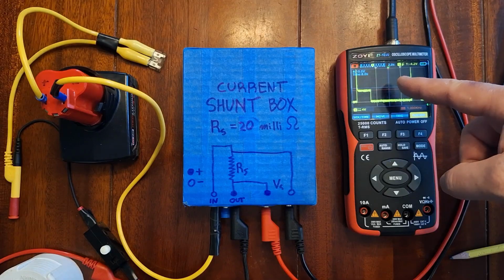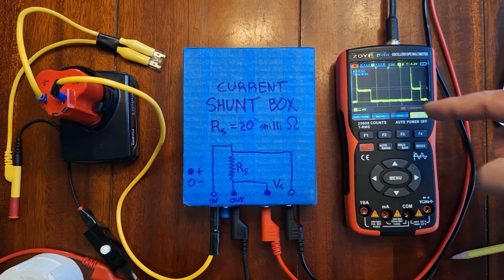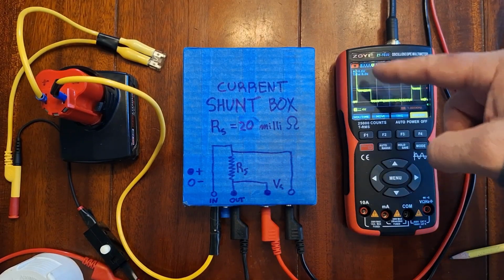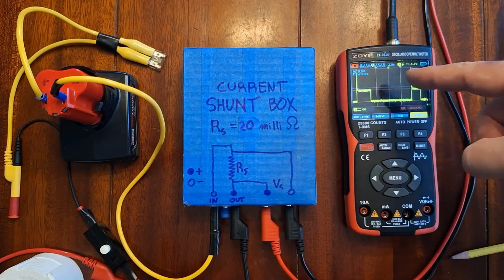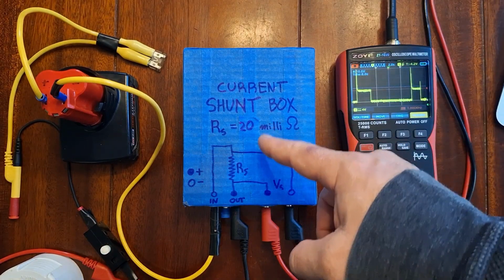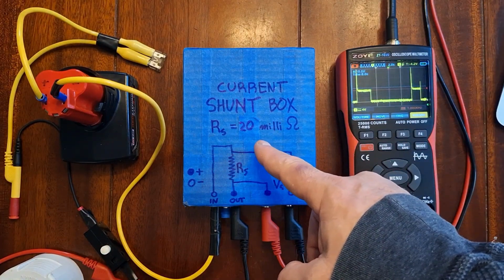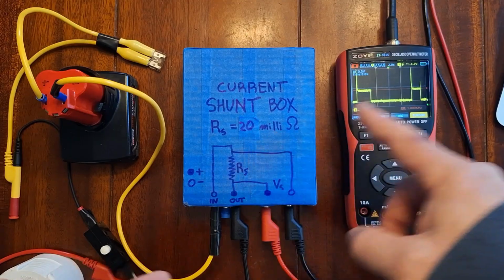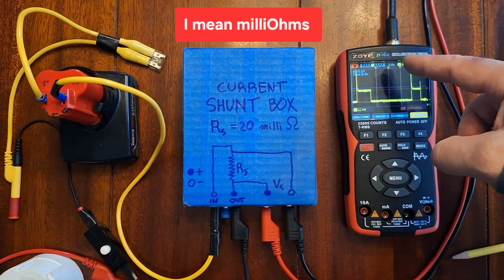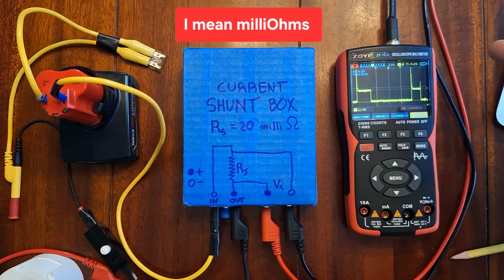Of course, you could also just set this to the millivolt scale without the 100-time probe and just read it as millivolts. So if you got 100 millivolts and you knew you had a 20 milliohm shunt, you could pretty easily figure out that that's 5 amps.